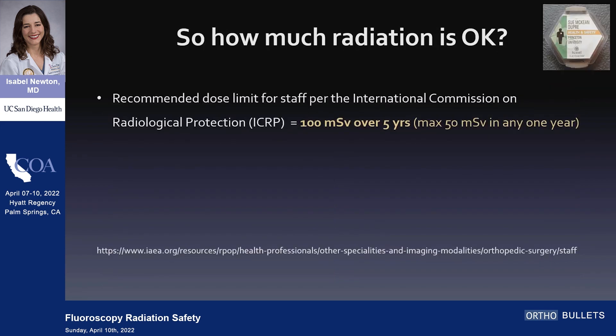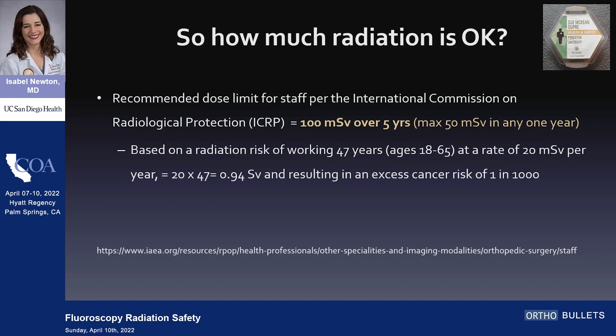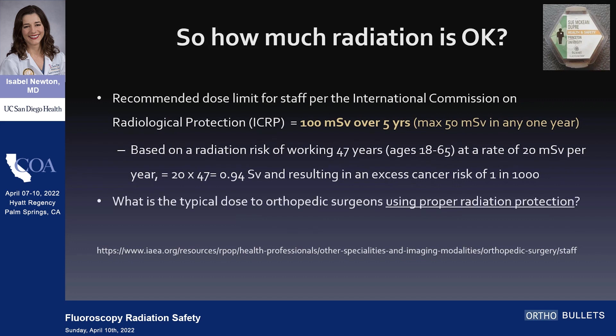How much radiation is okay? The International Commission on Radiologic Protection recommends 100 millisieverts over five years, or a max of 50 millisieverts in any one year. If you are wearing your radiation detector, you will be monitored and alerted if you exceed these levels. This is based on a radiation risk of working for 47 years starting at age 18, at a rate of 20 millisieverts per year, which is estimated to give an excess risk of cancer of 1 in 1,000. The typical dose to you using proper radiation protection is less than 2 millisieverts per year — but we don't know that any low dose is truly safe.